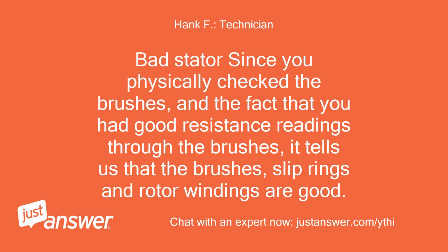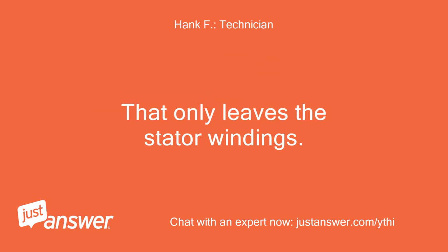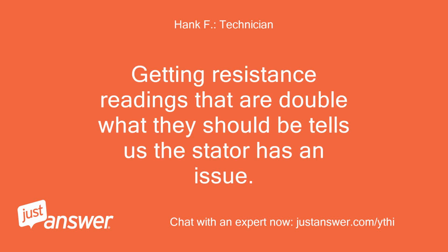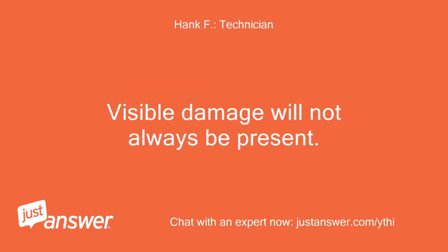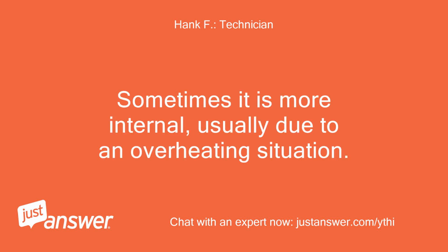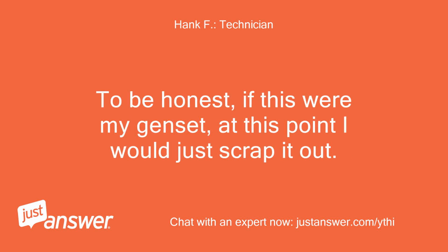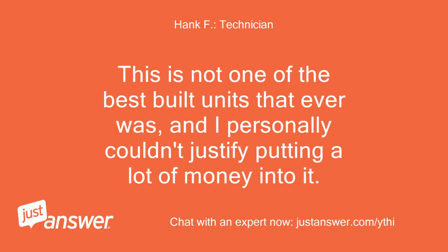4. Bad stator. Since you physically checked the brushes, and the fact that you had good resistance readings through the brushes, it tells us that the brushes, slip rings and rotor windings are good. That only leaves the stator windings. Getting resistance readings that are double what they should be tells us the stator has an issue. Visible damage will not always be present. Sometimes it is more internal, usually due to an overheating situation. To be honest, if this were my genset, at this point I would just scrap it out. This is not one of the best built units that ever was, and I personally couldn't justify putting a lot of money into it.